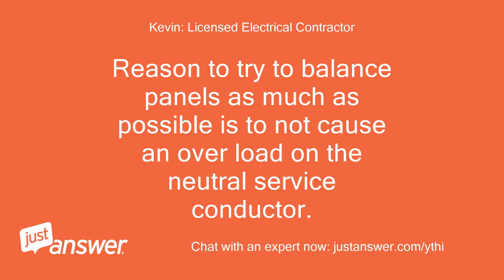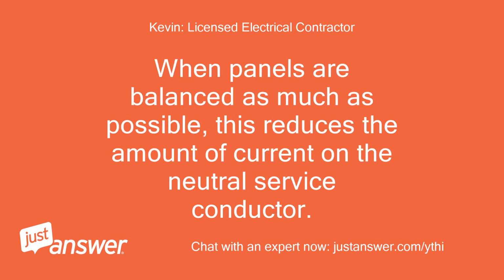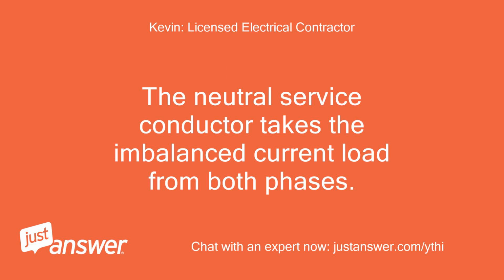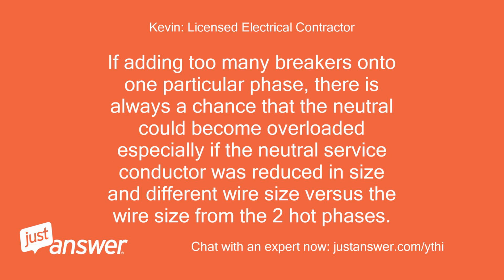Reason to try to balance panels as much as possible is to not cause an overload on the neutral service conductor. When panels are balanced as much as possible, this reduces the amount of current on the neutral service conductor. The neutral service conductor takes the imbalanced current load from both phases. If adding too many breakers onto one particular phase, there is always a chance that the neutral could become overloaded, especially if the neutral service conductor was reduced in size and different wire size versus the wire size from the two hot phases.